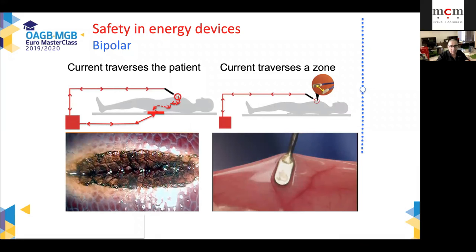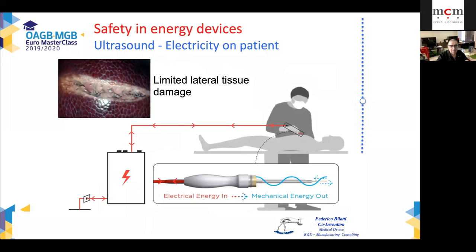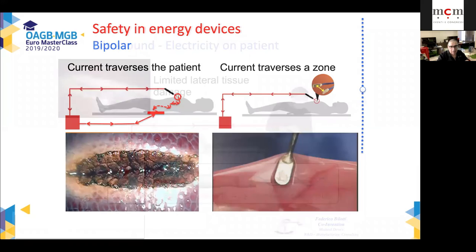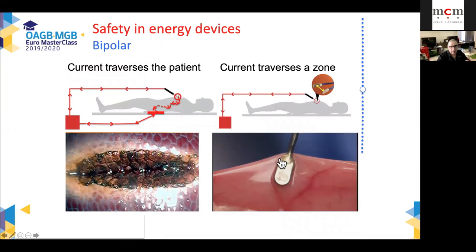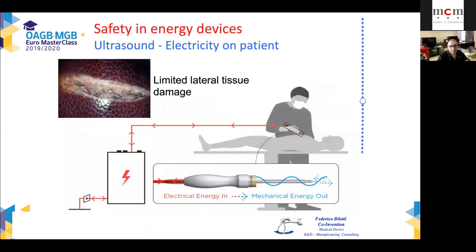Here we see on the left monopolar damage to the tissue, and to the right the bipolar damage to the tissue. And how the, okay, let's look at that aspect one more time. How the bipolar is causing the electricity to run sideways instead of straight between the jaws of the device. We don't see it because this video is not working. Let's describe this other aspect which is more critical. Ultrasound. This is the damage to the tissue by ultrasound. Certainly different than the carbonized tissue of the monopolar instruments.